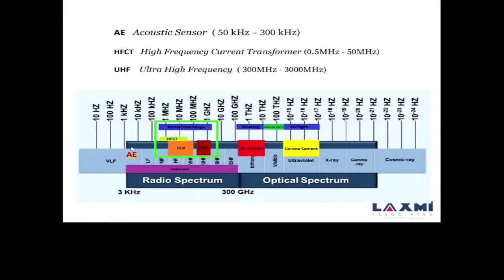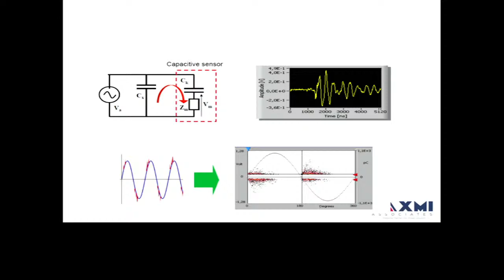So different methods are there, different sensors are there, and accordingly the ICs are different. Basically, if you talk about partial discharge, it has a wide band measurement, starting from 50 kilohertz to 300 gigahertz. That's the band, and 4-5 sensors clubbed together give you complete information about the PD activity inside a transformer or any asset. Here what you are seeing is a band where HFCT is in the megahertz band, TEV in the megahertz band, UHF in the gigahertz band, and acoustic in the kilohertz band. Overall, by doing this PD, you will get a clear picture of the transformers.